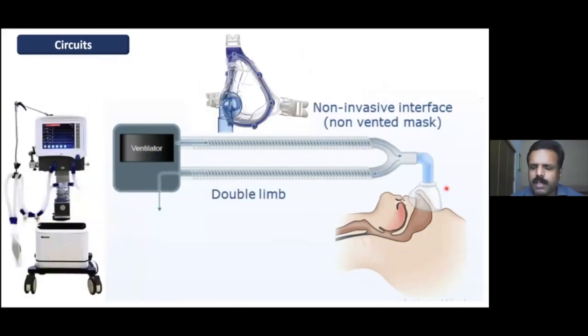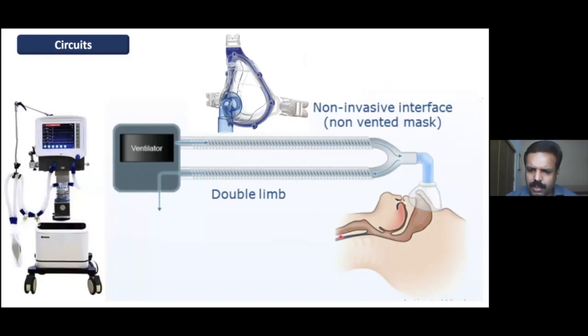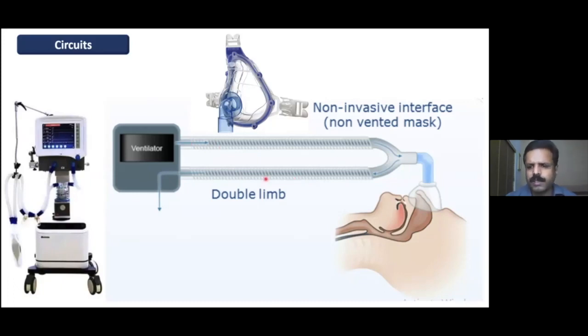In a dual limb circuit, there is an inspiratory port through which gas goes in, and the patient exhales gas through the expiratory limb. This is typically used with an ICU ventilator in non-invasive ventilation mode. When using a dual limb circuit, the mask must be non-vented — there should be no air leak from the mask, because there is a dedicated expiratory port.